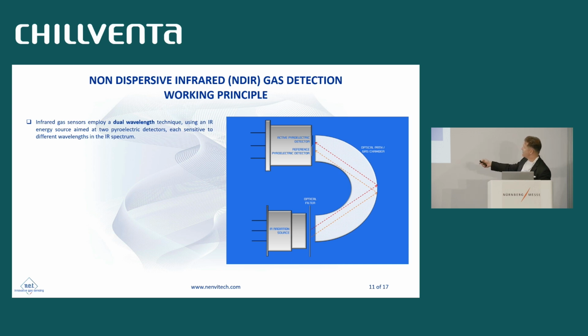On the other hand, we have a pyroelectric detector. A pyroelectric detector is an optoelectronic component able to measure energy at a specific wavelength. So we select one detector, which is called the active detector, at the precise frequency of absorption of the target gas, for example, R32. Then we select a second pyroelectric detector, which is called the reference, in an area of the spectrum where there's no absorption for that specific gas.